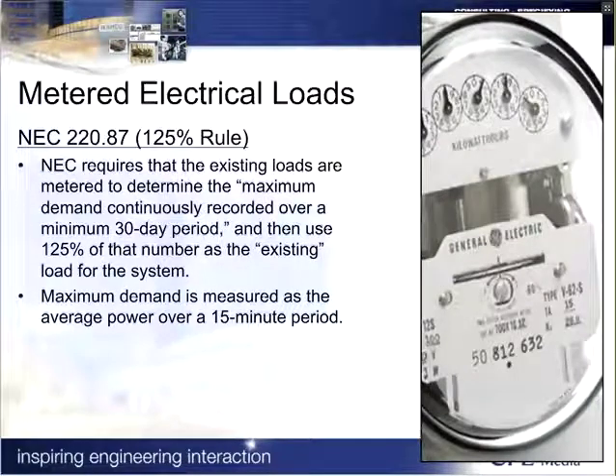Just a little reminder that the NEC has a nice little rule for existing installations. We can measure an existing installation for 30 days continuous and then use 125% of that number to figure out what the existing load is on a building. And this could be applied to the size of your generators where you're working on an existing installation.